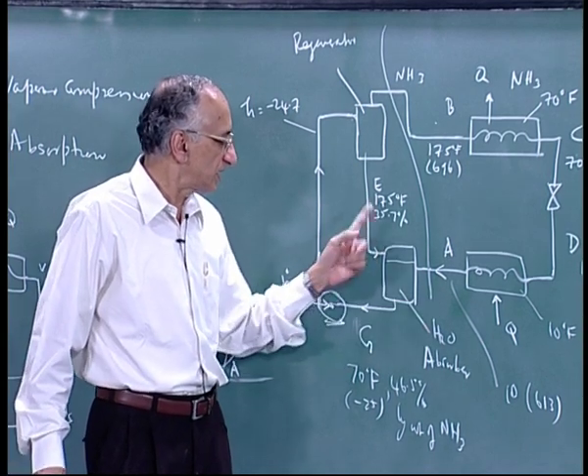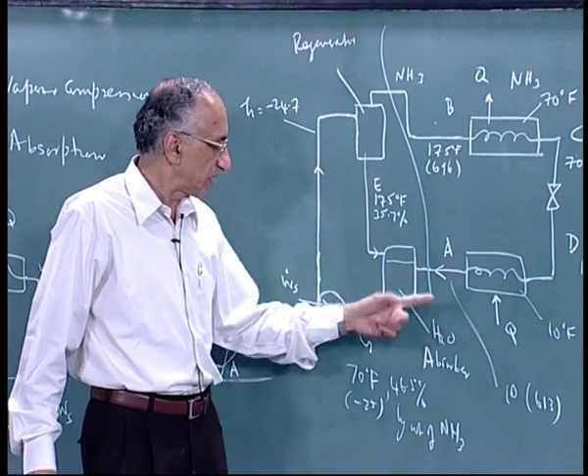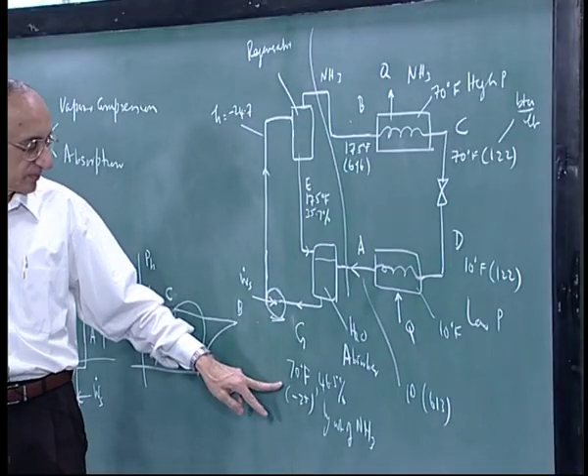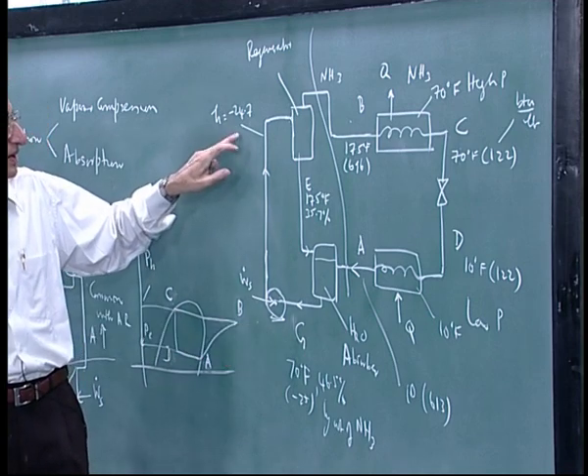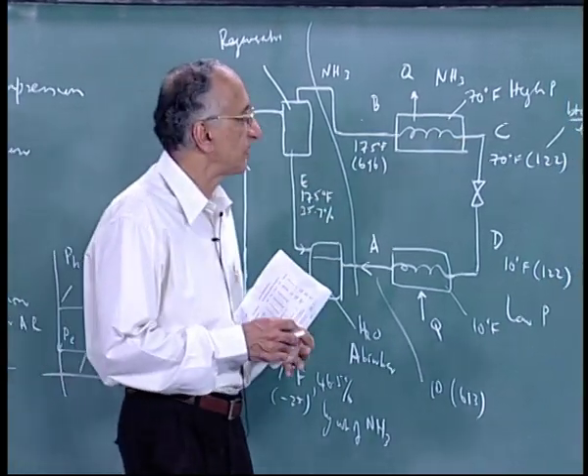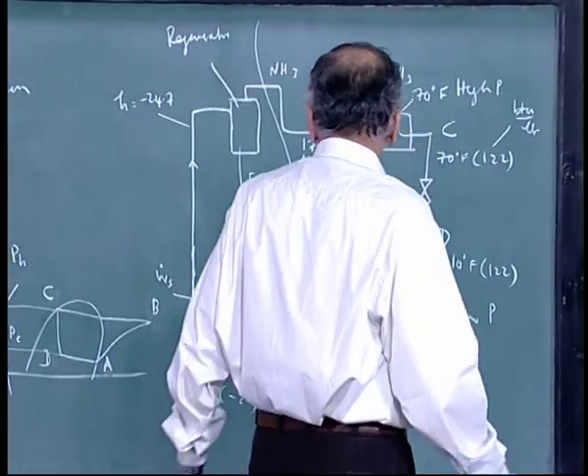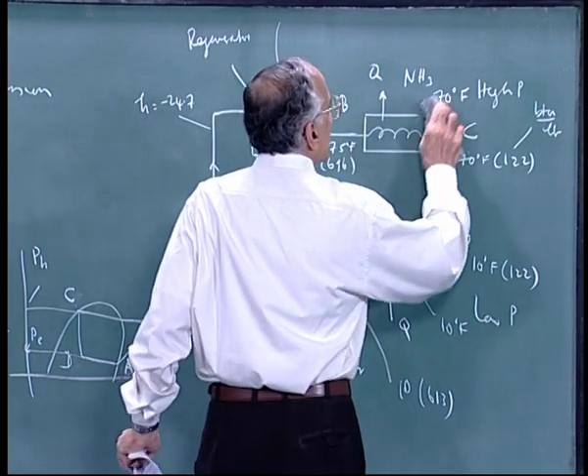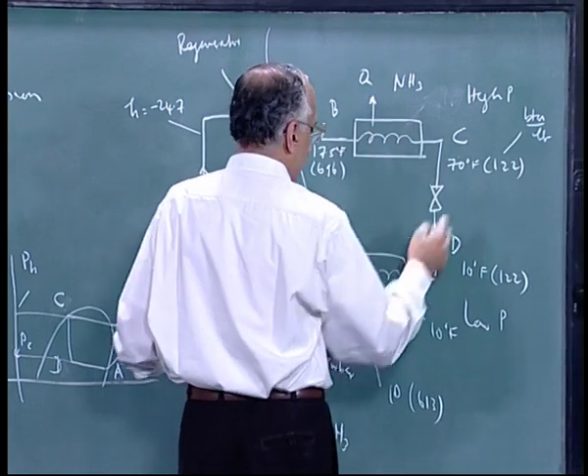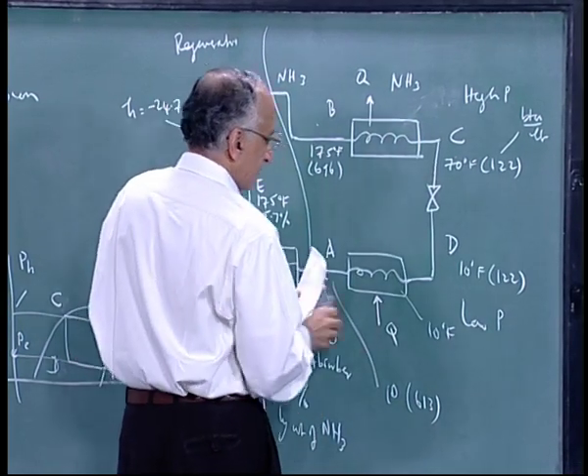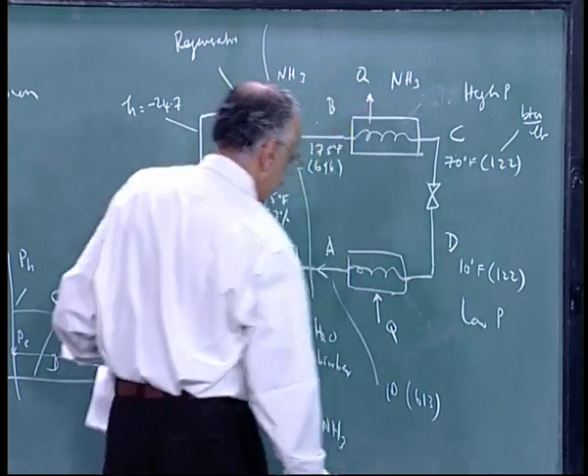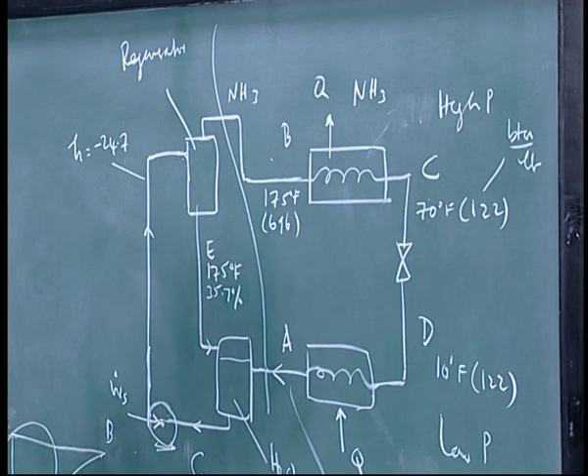The temperatures — 10°F in the evaporator and 175°F in the regenerator — determine a final absorber temperature of about 70°F. The ammonia that comes out of the regenerator is at 175°F and finally cools to about 70°F at the condenser. The high pressure corresponds to 70°F, the low pressure corresponds to 10°F. The pressures are 128 PSI absolute (high) and 38 PSI absolute (low), all taken from the ammonia chart.